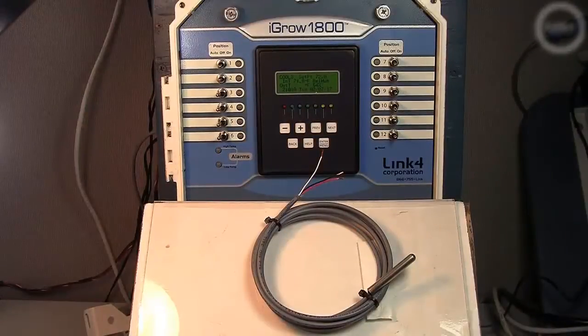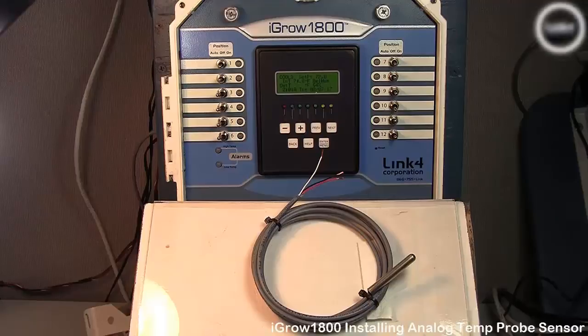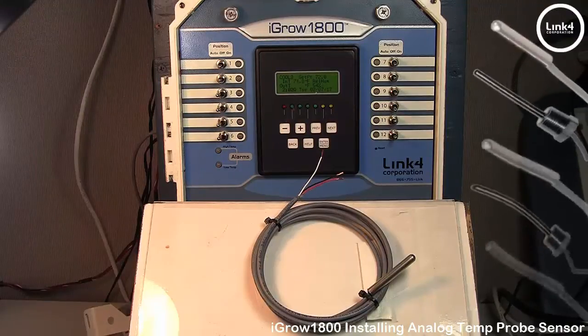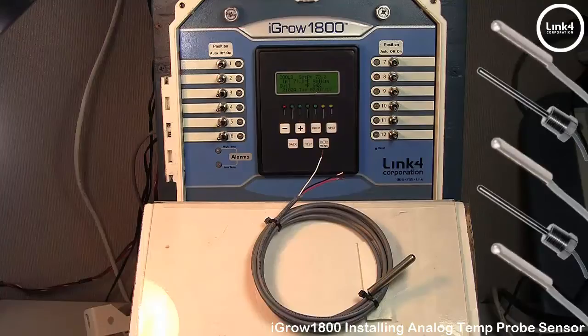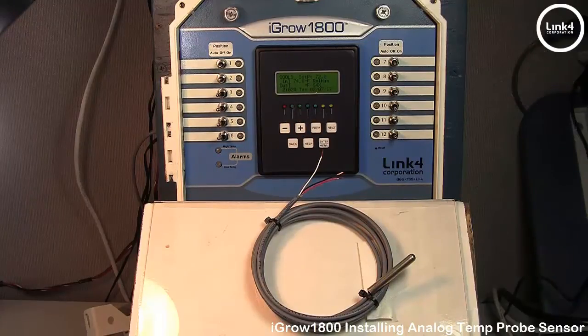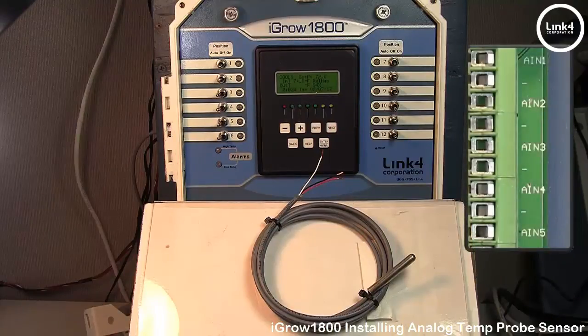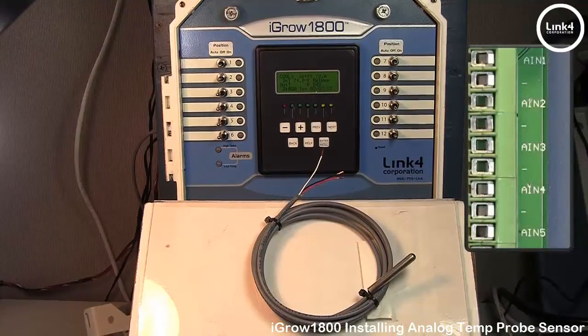In this video, we will be installing the analog temperature probe on the iGrow 1800 controller. Now, with this controller, you can install up to 5 temperature probes, and they can be used for various purposes. For bottom heat, mixed valves, microzones, and much, much more.